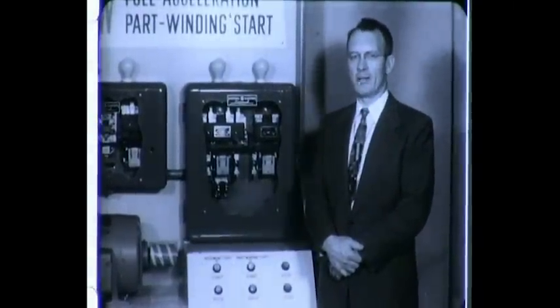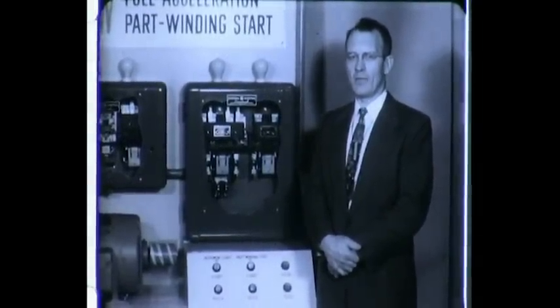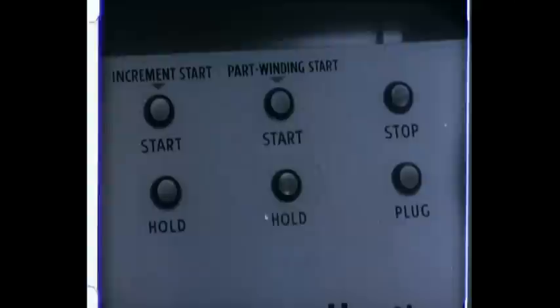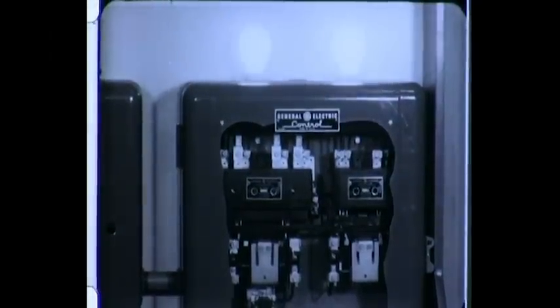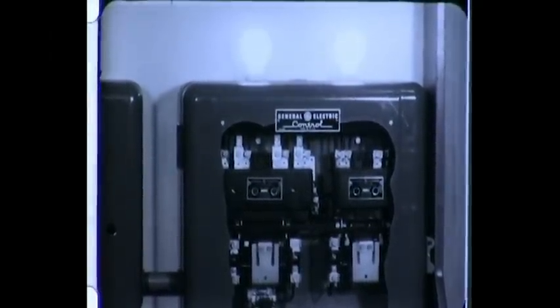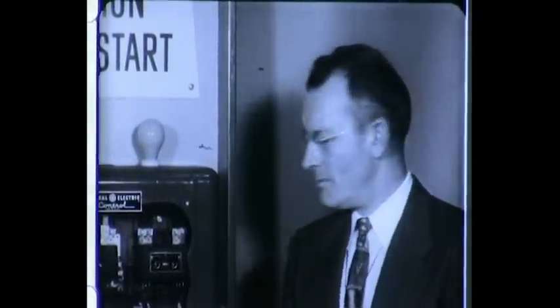Produces considerable flicker. Now, let's see how the new full acceleration method works. Less flicker. Another benefit is less motor heating. With full acceleration part winding starting, the heating generated on the part winding connection is no greater than that encountered for normal across-the-line starting. Acceleration is smoother, and as I'll demonstrate, there's less noise. First, listen to the conventional method.